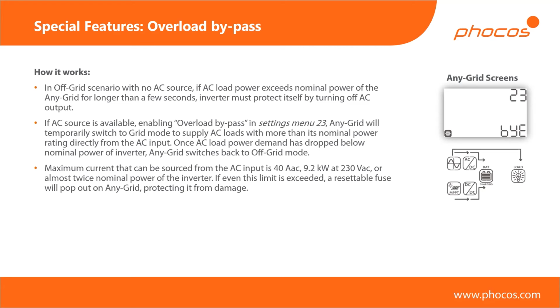So let's say you are in the scenario where you have a connection to the grid. Obviously, if you don't have any connection to the grid, and you don't have any other AC source, then if you're overpowering your inverter, it can only shut down to protect itself. If you're demanding more than 5 kilowatts for a long period of time, the inverter will simply turn off. If, however, you do have an AC source which is capable of sustaining 5 kilowatts or more, then if you activate the overload bypass on the AnyGrid, as soon as it senses that it's no longer able to cope with your energy demand, it will simply switch to grid mode. Then it's bypassing the whole inverter entirely, passing the power directly from the grid to your loads. And it can do this very quickly, at the same speed as typical switchover times of 10 milliseconds if you're in UPS mode, which you probably are in most cases.